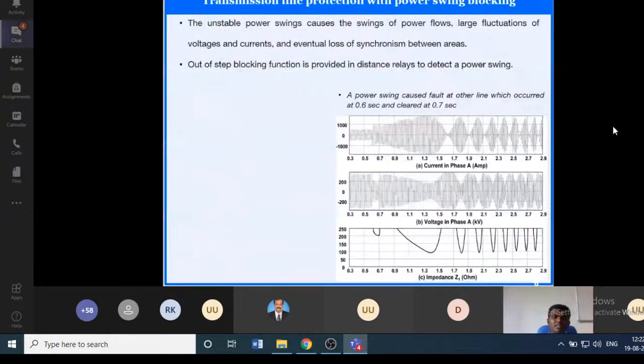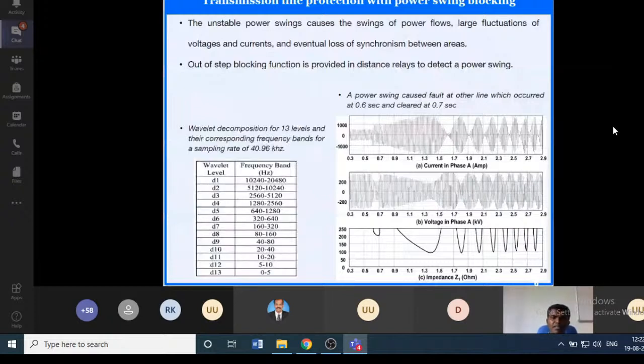The other challenge is, when power swing occurs, we can use a power swing blocking method, so we can block the trip due to the power swing. But if a fault occurs once again in the particular line during the power swing, then we cannot detect the fault, since we are applying the power swing blocking. These problems can be sorted out using the wavelet transform decomposition.